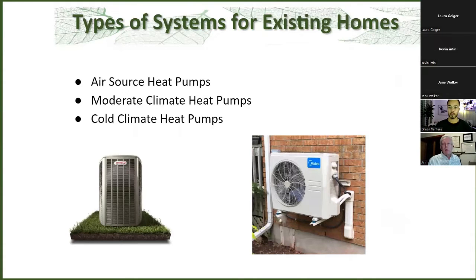Today we're looking at air source heat pumps, and there are two main categories: what we call moderate climate and cold climate. The moderate climate heat pumps work down to around just below freezing, and they're more popular in the southern U.S. areas where people are more concerned about cooling than heating. But for Canada, we're really focused on the cold climate heat pumps that work down to as low as minus 30, such as the one I have that I'll be talking about later.